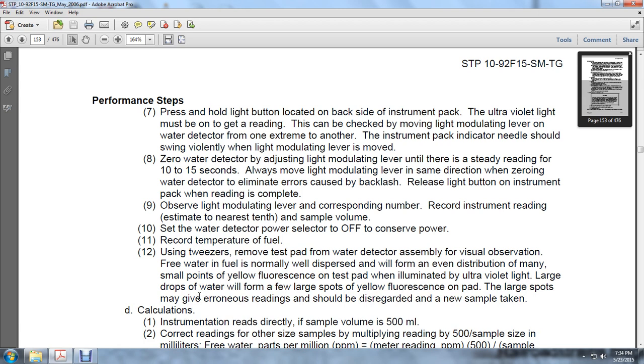Free water in the fuel is normally well dispersed and will form an even distribution of many small yellow fluorescent points on the test pad while illuminated by the ultraviolet light. Large drops of water will form a few large yellow fluorescent spots on the pad. The large spots may give an erroneous reading and should be disregarded, and a new sample taken.